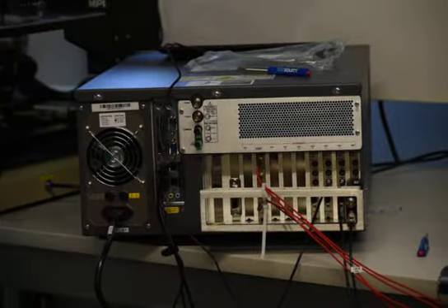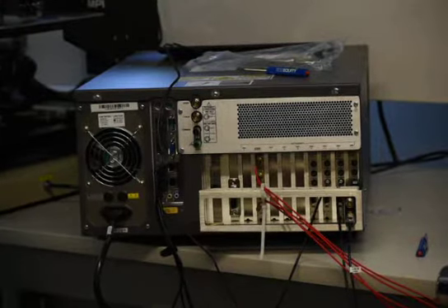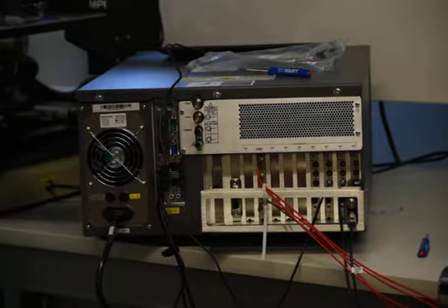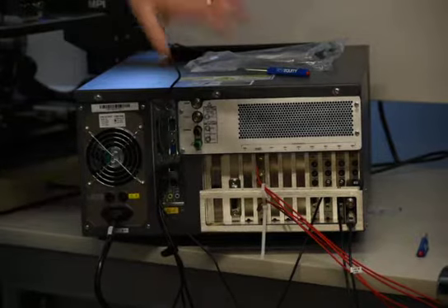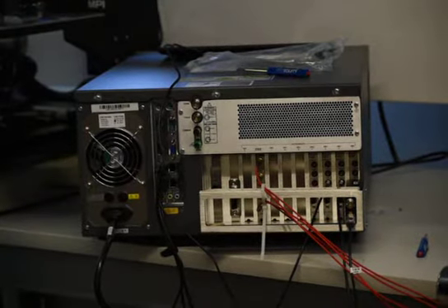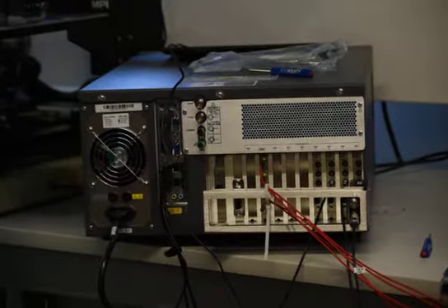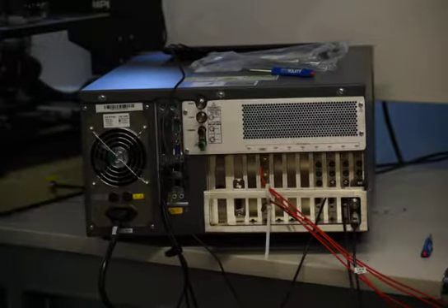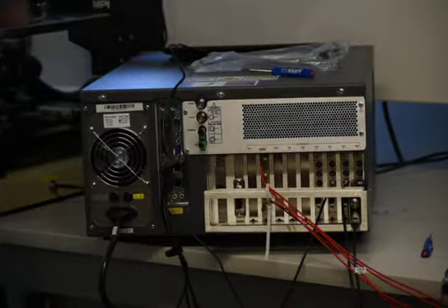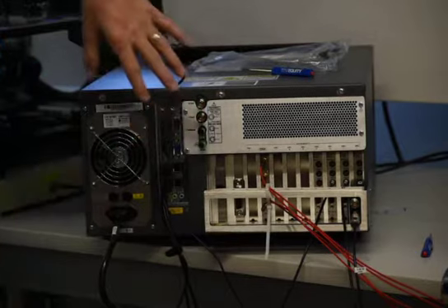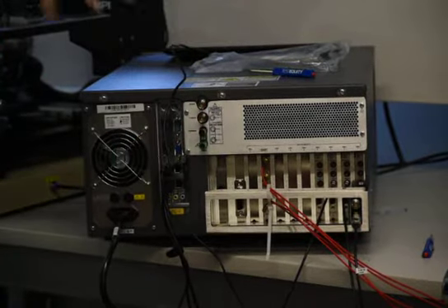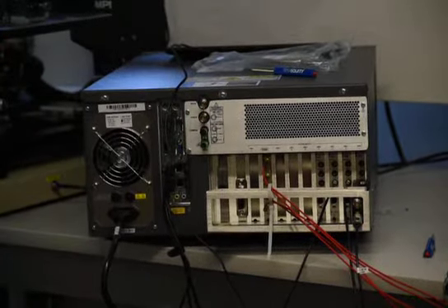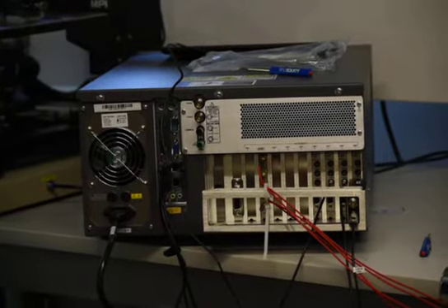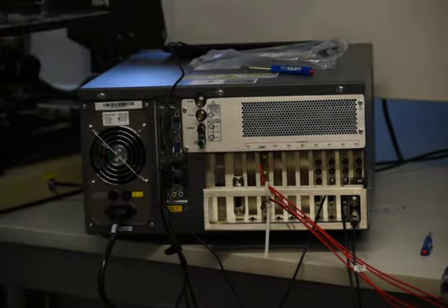Because somebody will get hit and they'll call us and they'll blame us. No, it's doing what it's supposed to do. The system is off. It's your device that's not off. Your device will have a charge on it still. Most equipment has low enough impedance that when you turn it off, there's still low enough impedance in the instrument that it will naturally discharge your device. This won't do that. Okay, just so you understand that.